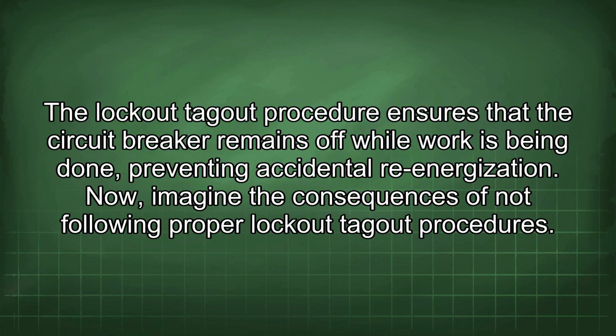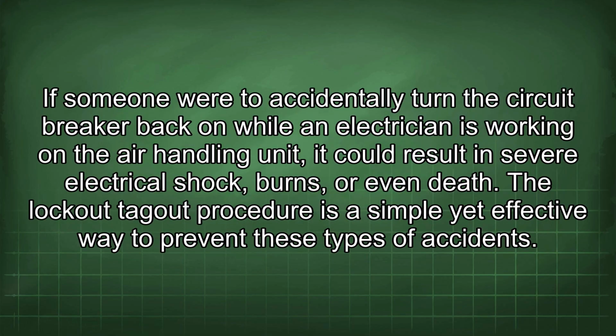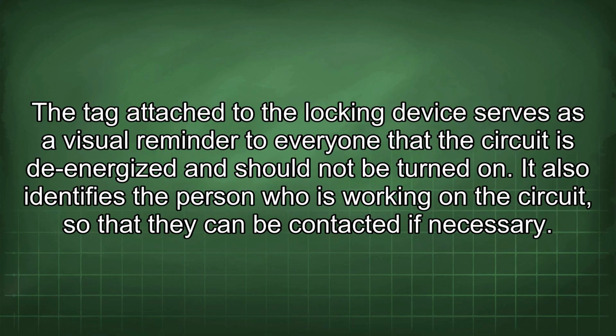Now, imagine the consequences of not following proper lockout tag-out procedures. If someone were to accidentally turn the circuit breaker back on while an electrician is working on the air handling unit, it could result in severe electrical shock, burns, or even death. The lockout tag-out procedure is a simple yet effective way to prevent these types of accidents. The tag attached to the locking device serves as a visual reminder to everyone that the circuit is de-energized and should not be turned on. It also identifies the person who is working on the circuit so that they can be contacted if necessary.